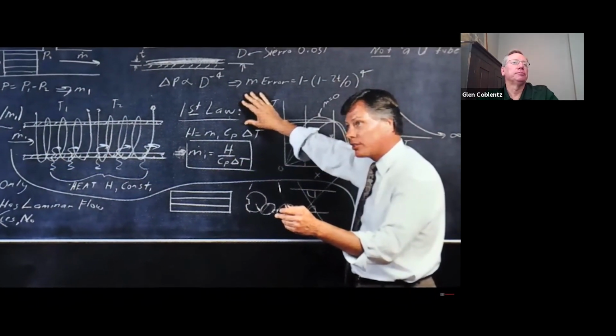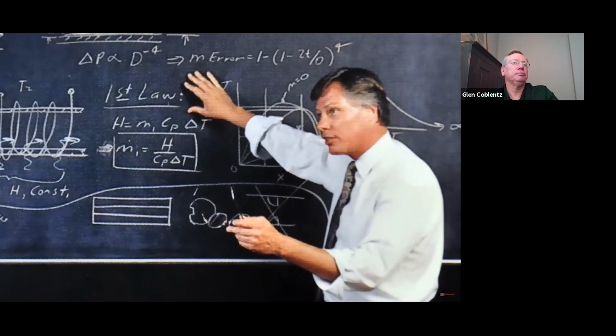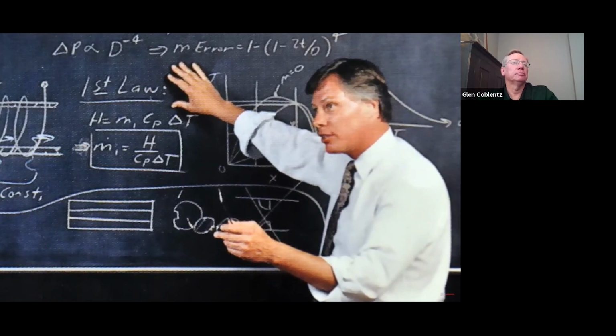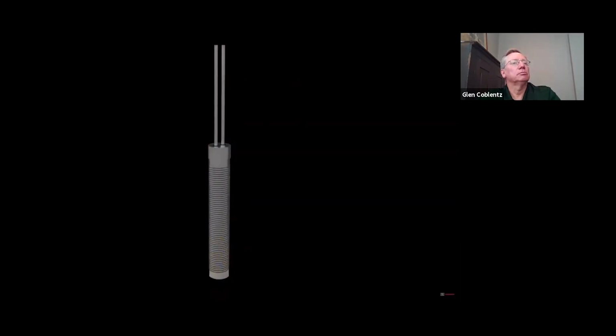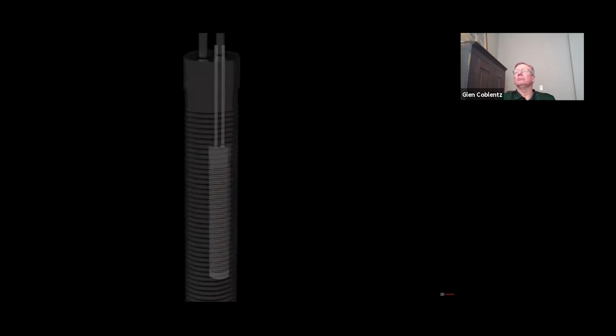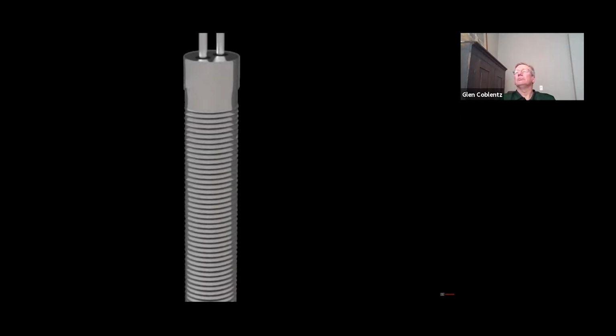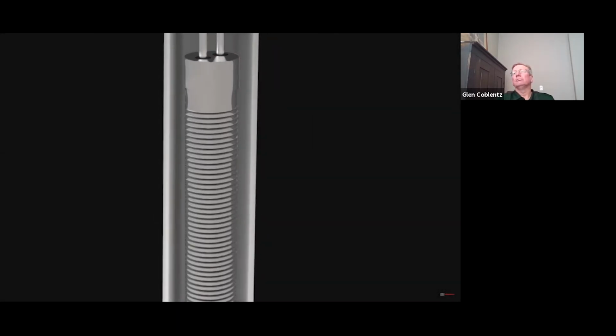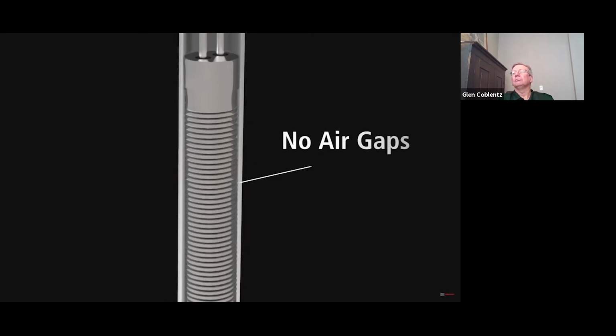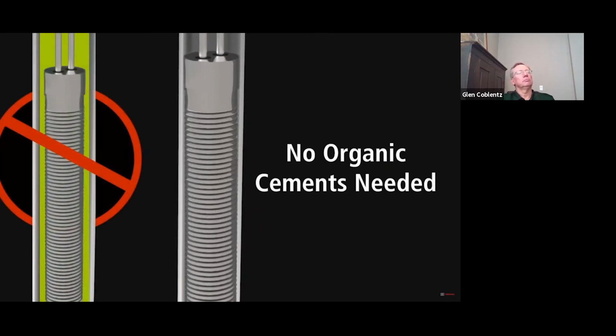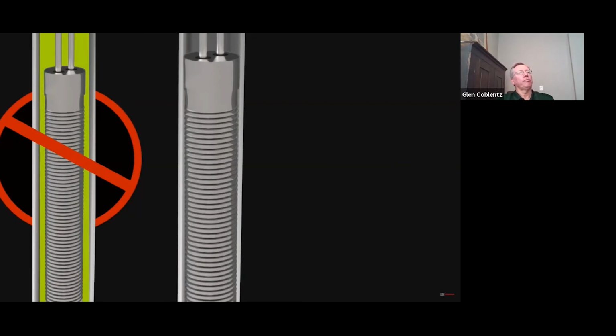Dr. Olin believed there had to be a better way. He needed to get rid of all cements to make the most stable thermal sensor in the world. After many years of experiments and testing, the answer finally revealed itself. On March 9, 1999, Dr. Olin patented a breakthrough thermal sensor design. Like other thermal mass flow sensors, it was made of a platinum resistance temperature detector wire wound around a ceramic mandrel. But this is where the similarities ended. Through a proprietary, highly controlled manufacturing process, a metal sheath is tightly formed on the mandrel and wire assembly to be in such intimate contact that no air gaps exist and no organic filler cements are needed. This new sensor was literally all metal.